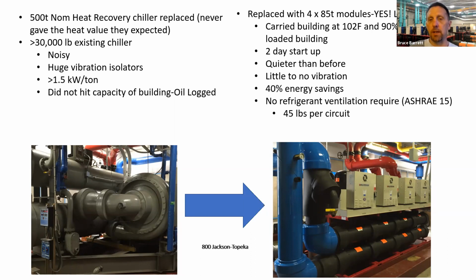The change out, by the way, did not require refrigerant ventilation in that equipment penthouse because of our 45 pounds of charge in each circuit. So the ASHRAE calc is based on the largest refrigerant charge. So it's 45 pounds. Well under the requirement in that large mechanical room.